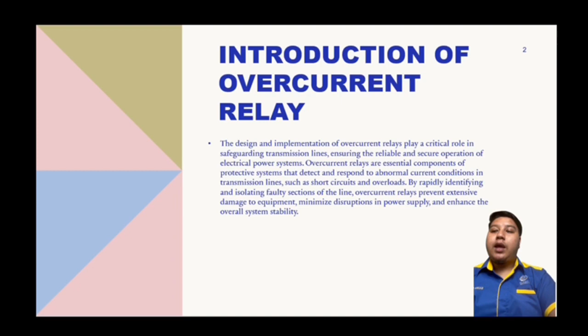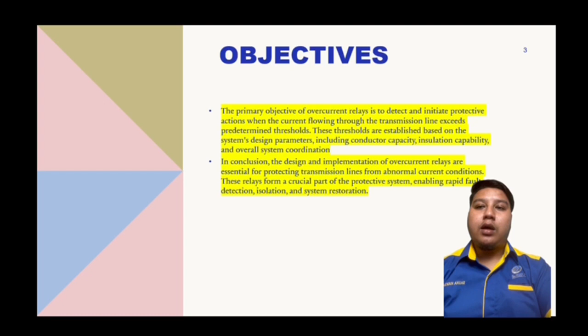The primary objective of overcurrent relays is to detect and initiate protective action when the current flowing through the transmission lines exceed predetermined thresholds. These thresholds are established based on the system design parameter, including conductor capacity, insulation capability, and overall system coordination. In conclusion, the design and implementation of overcurrent relays are essential for protecting transmission lines from abnormal current conditions. This relay form a crucial part of the protective system, enabling rapid fault detection, isolation, and system restoration.